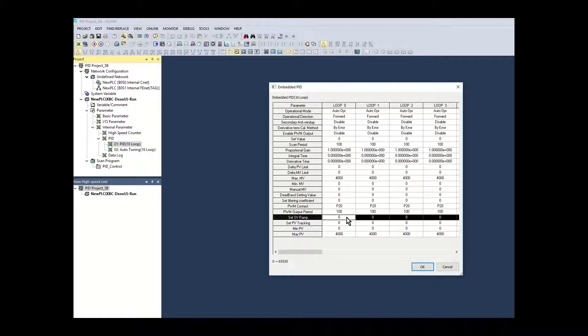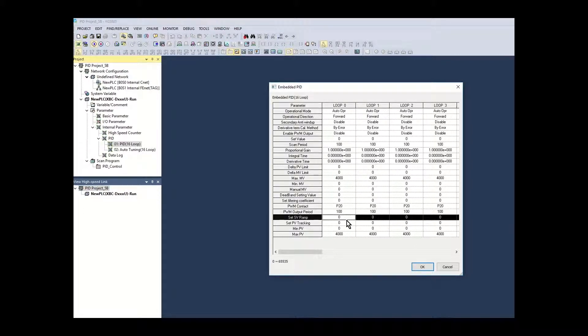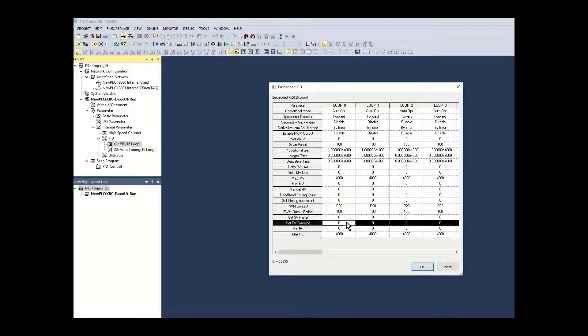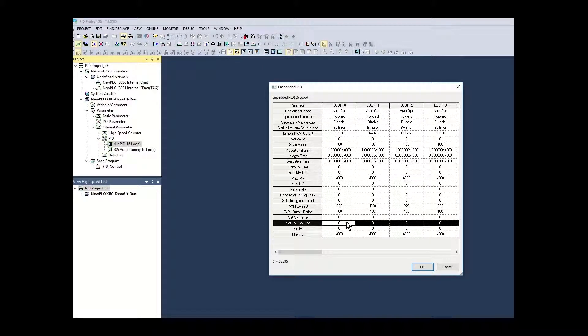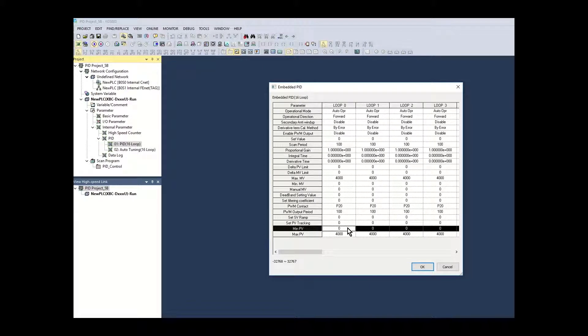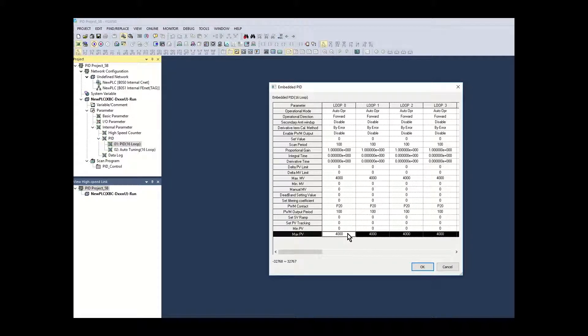The SV ramp is left at the default value of zero. The PV tracking is left at the default value of zero. The min and max PV values are left at the full range of the PID loop.